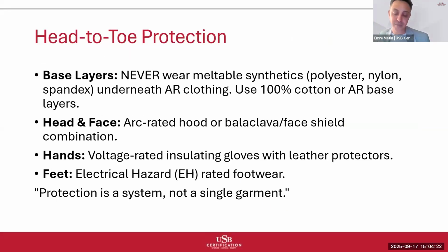Head-to-toe protection system. Arc flash protection requires a complete head-to-toe approach because the thermal hazard affects the entire body simultaneously. Let me walk through the complete protection system. Base layers. Never wear meltable synthetics underneath arc-rated clothing. Use 100% cotton or arc-rated base layers. Head and face. Arc-rated hood or balaclava and face shield combination must be used.